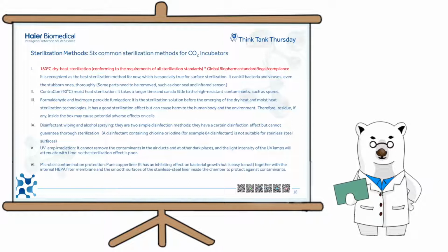Your light source would need to have unrestricted access to all surfaces of the incubator chamber, shelves, and shelf-mounting hardware, etc. A shadowed region will not be decontaminated by UV light. And also, a common method for microorganisms to survive UV exposure is through enhanced DNA repair mechanisms. In this case, survivors of a UV cycle could be more likely to survive a repeat treatment. Plus, UV light is generally not effective in destroying endospores.